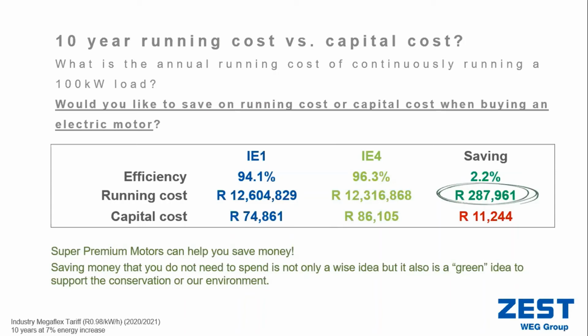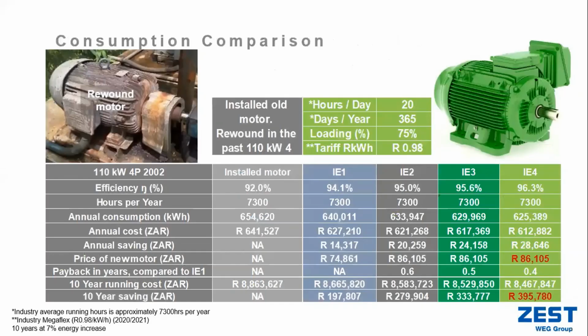Then again, I look back at the capital cost, because that's often where we nowadays focus. We always say we need to reduce our expenditure. And buying an IE1 versus an IE4, there was only a difference of 11,244 Rand when a motor was purchased. Then we took it a step further, and we said, you know what? It's always good to compare a brand new IE1 motor with a brand new IE4 motor that is of the latest design and the latest construction and of the highest efficiencies.